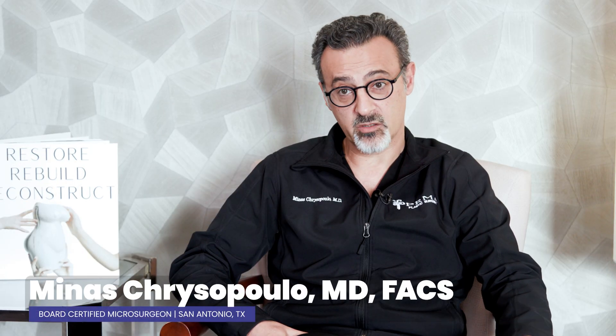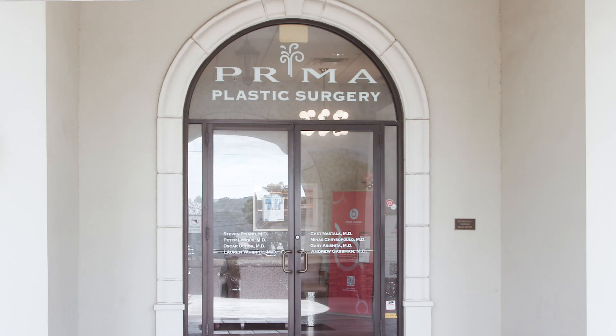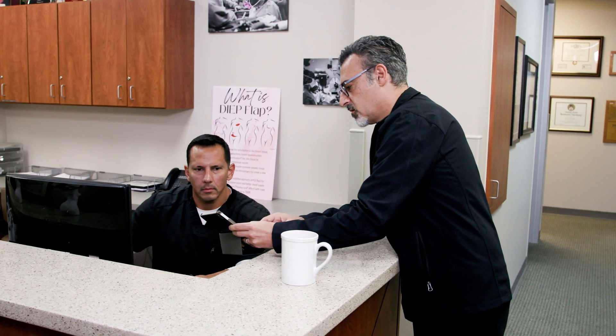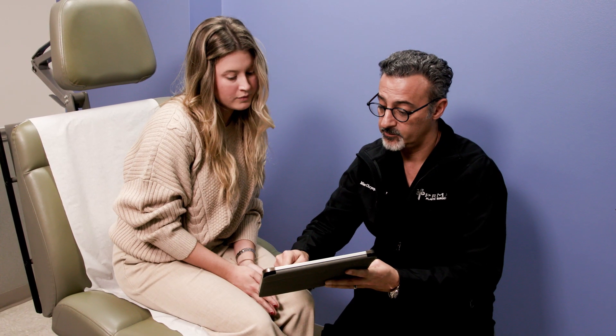We do a lot of tissue transplantation for breast reconstruction. Breast reconstruction can be performed in different ways — the most common technique uses implants. We actually specialize in tissue transplant procedures that involve taking tissue from one part of the patient's body and transplanting it to the chest to reconstruct a new natural breast. These complex procedures involve microsurgeries, so you have to restore blood flow so that the new tissue reconstruction survives. This is where T-STAT comes in, because it's an early warning system that alerts us at the earliest possible time if there's an issue with blood flow — because if you don't catch an issue, the tissue can actually die.